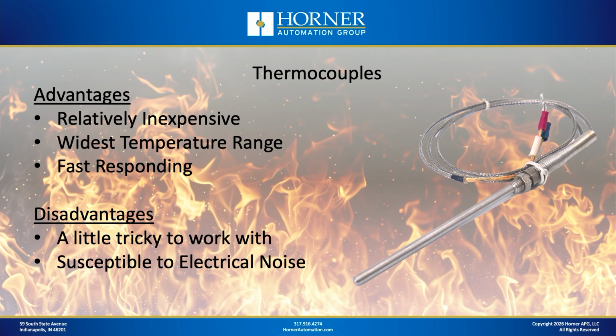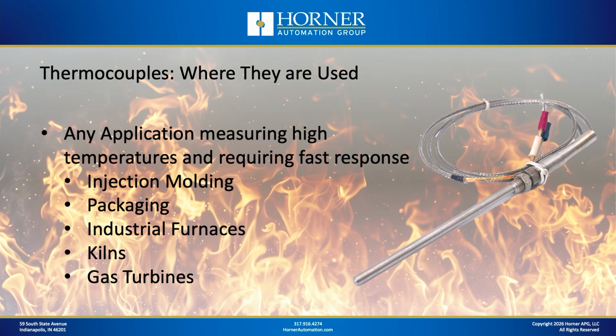These have been around forever. They have two primary advantages. Well, let's say three. They're pretty inexpensive, or they can be, but they've got the widest temperature range and they've got the fastest response of any temperature sensor. So again, if that's important in your application, wide temperature range, fast response, then you're probably going to be using a thermocouple. Now, it's not all sunshine and roses, however. They are a little tricky to work with, which you'll discover soon, and they can be susceptible to electrical noise because the signal that they generate is quite small.